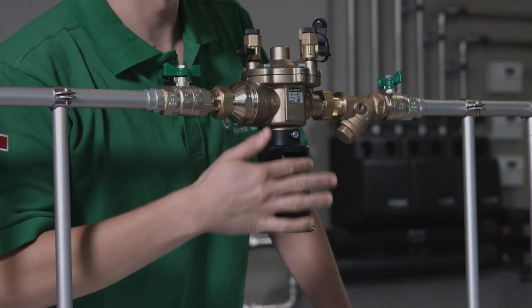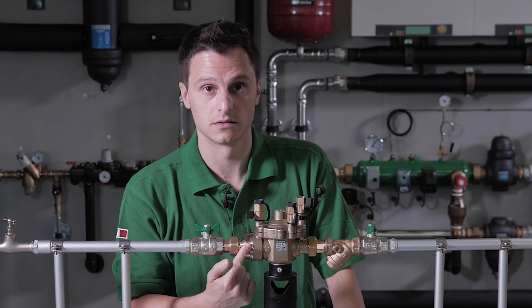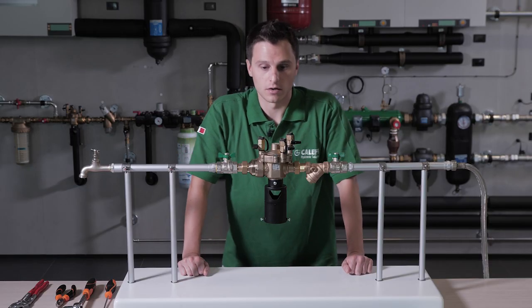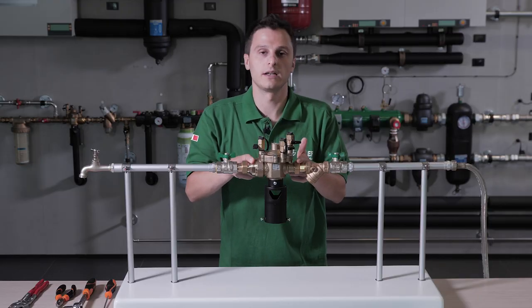If we detect a leakage from the discharge line, it means that the downstream check valve has failed. In case of failure of downstream check valve or upstream check valve, there are some basic operations to do, and now we will see them together.